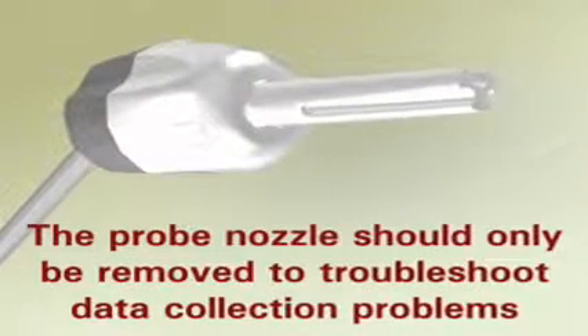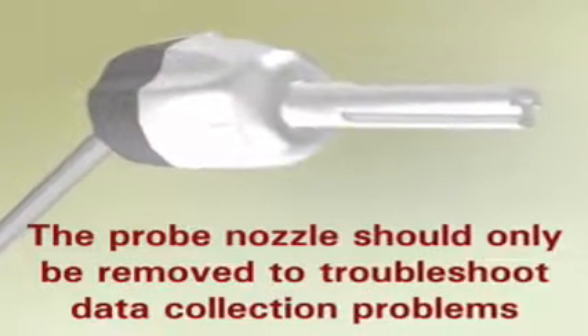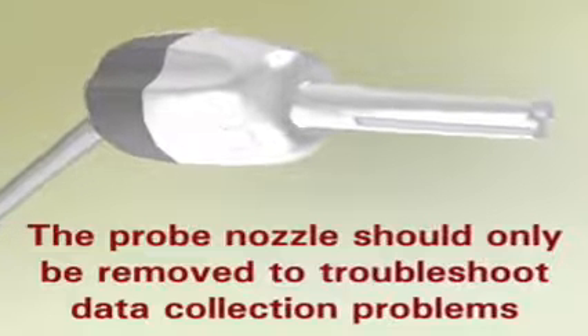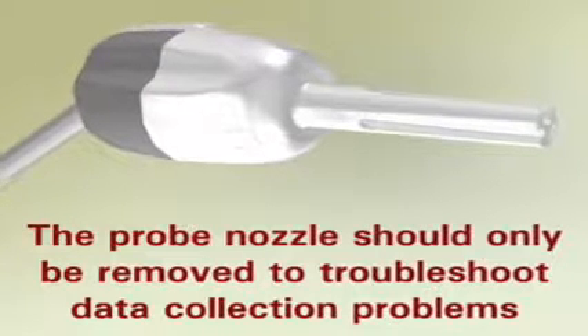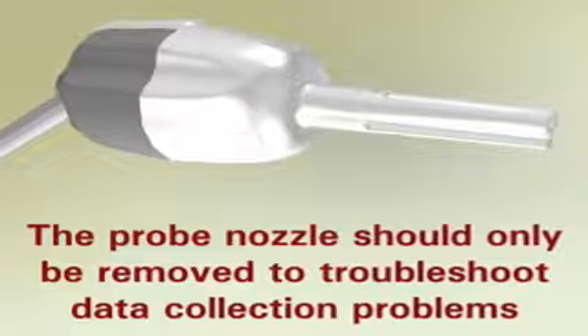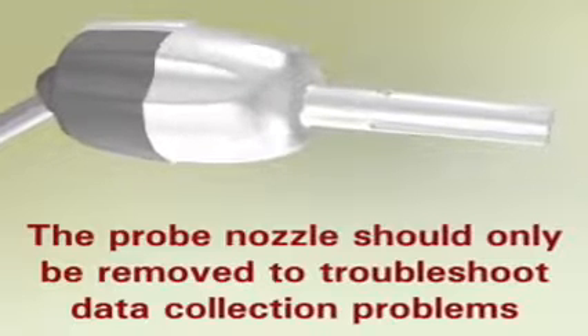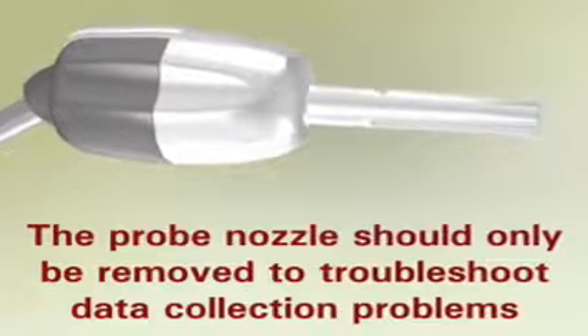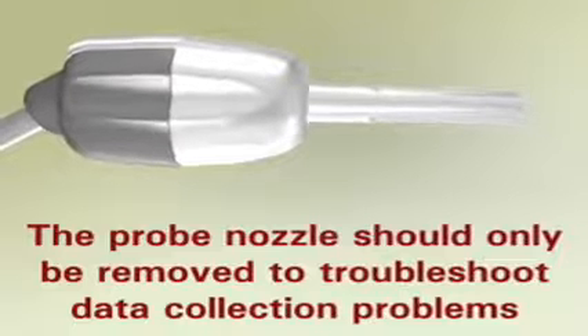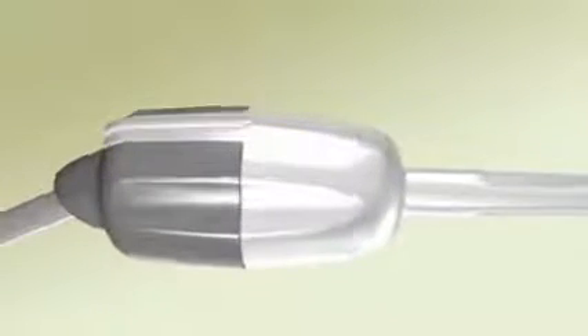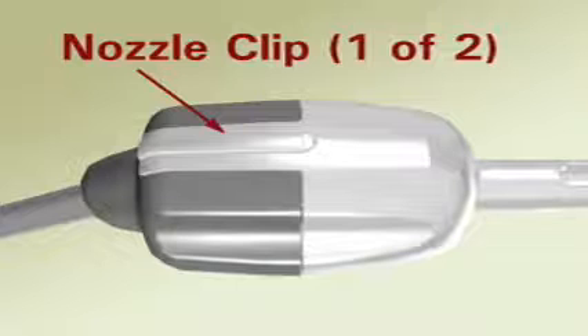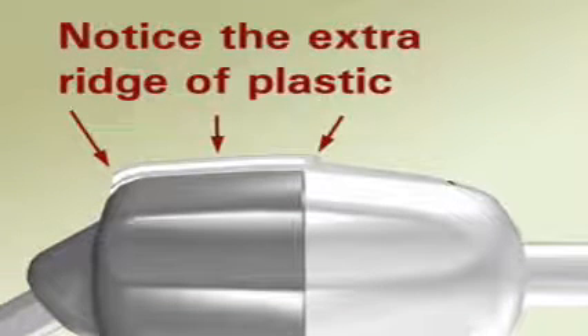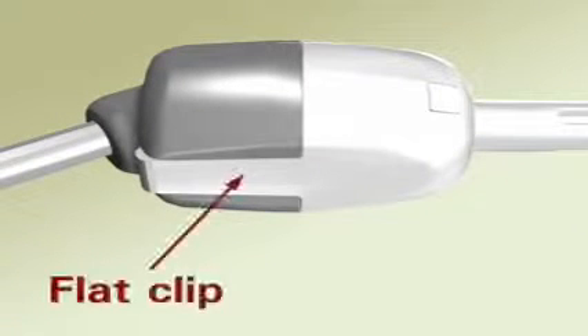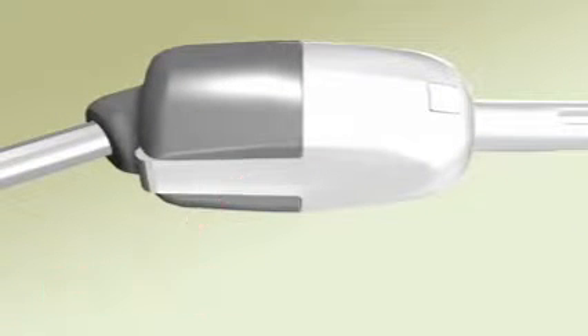The probe nozzle should only be removed to troubleshoot data collection problems. The clips that hold the nozzle on the probe body will become less effective after the nozzle has been detached a few times. When this occurs, the nozzle will have to be replaced. If the nozzle must be removed, locate the 2 small clips that secure it to the probe body. The top clip has a ridge of additional plastic on its surface. The bottom clip is flat and smooth to the touch.